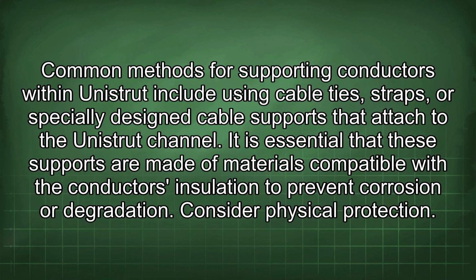Common methods for supporting conductors within Unistrut include using cable ties, straps, or specially designed cable supports that attach to the Unistrut channel. It is essential that these supports are made of materials compatible with the conductor's insulation to prevent corrosion or degradation. Consider physical protection.